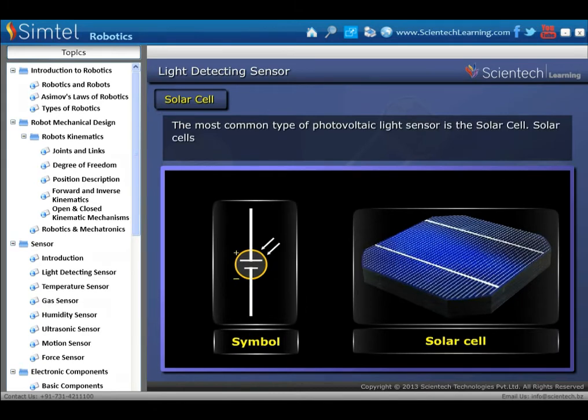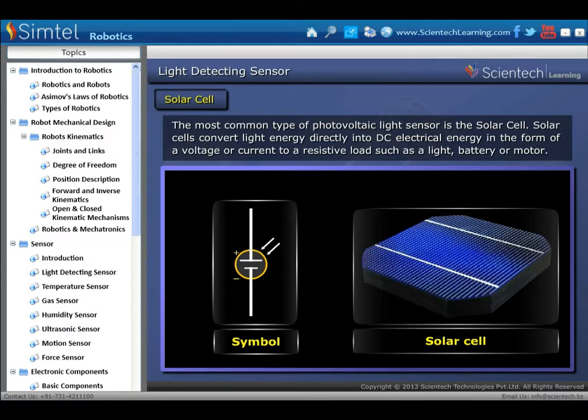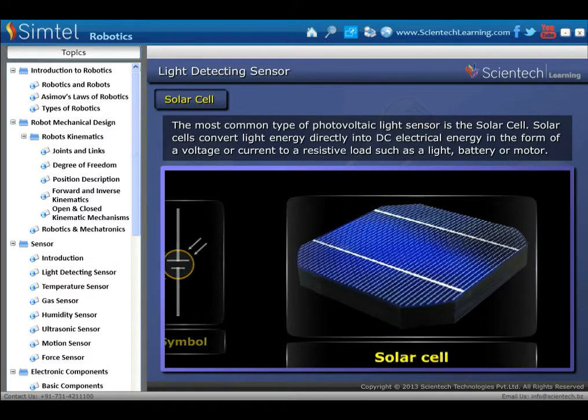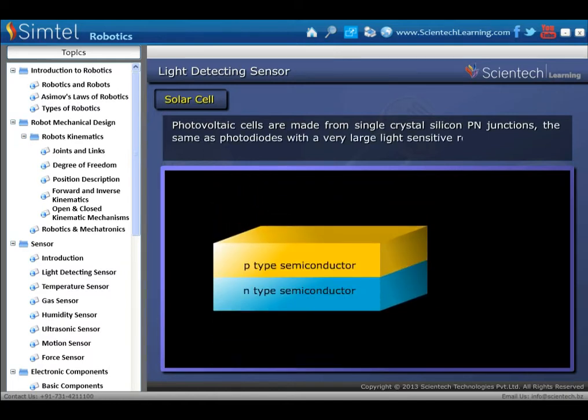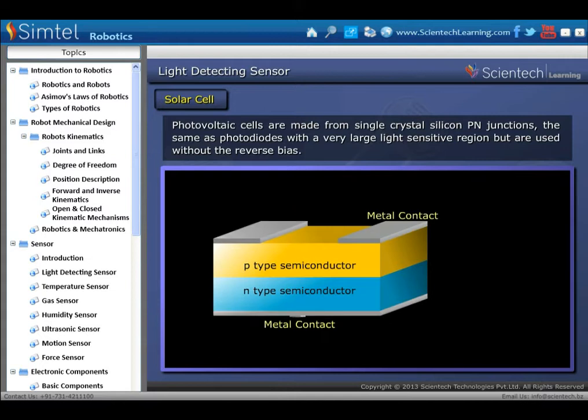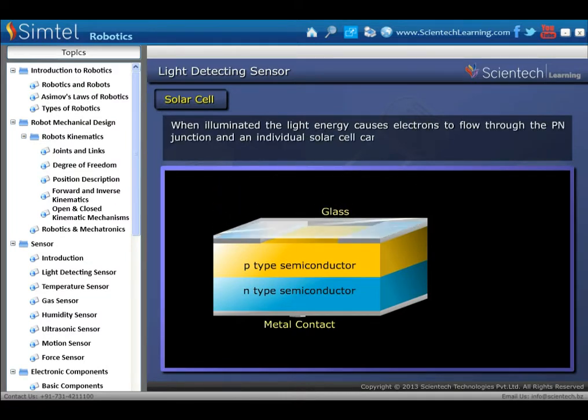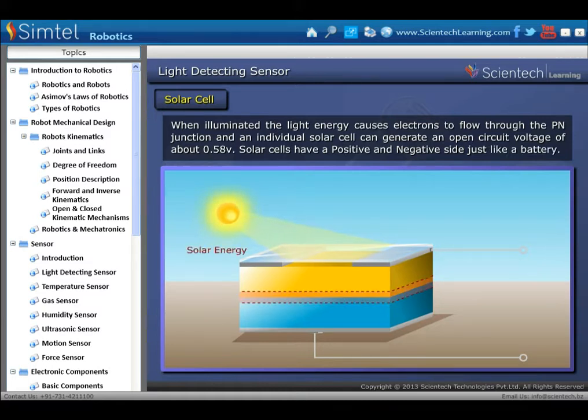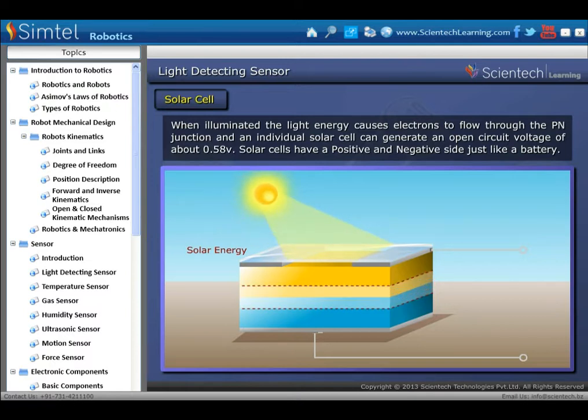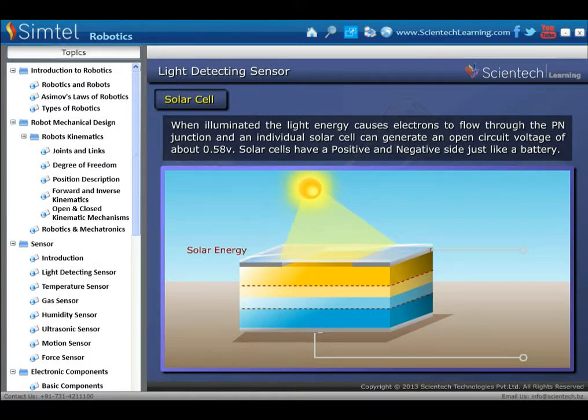The most common type of photovoltaic light sensor is the solar cell. Solar cells convert light energy directly into DC electrical energy in the form of a voltage or current to a resistive load such as a light, battery, or motor. Photovoltaic cells are made from single-crystal silicon PN junctions, used without the reverse bias. When illuminated, the light energy causes electrons to flow through the PN junction, and an individual solar cell can generate an open circuit voltage of about 0.58 volt. Solar cells have a positive and negative side, just like a battery.